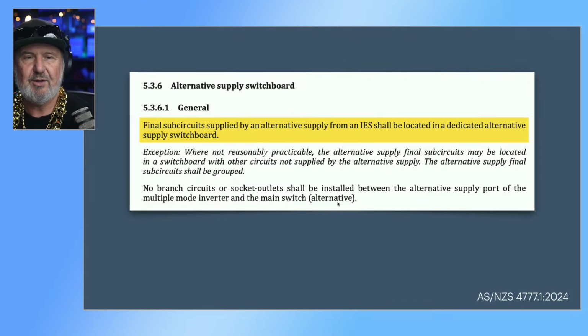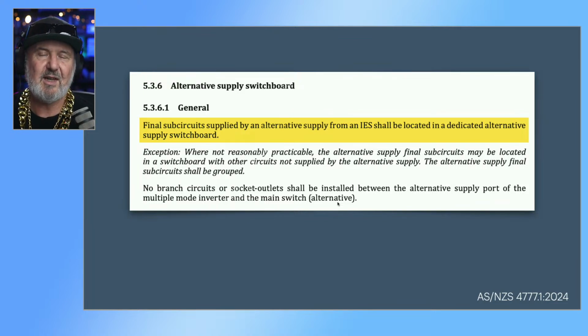So, alternative supply is the new supply naming used. Well, it's not that new to 3000, but it's new to 4777 part 1 for a backup circuit. If you have a hybrid inverter that has a backup, it's now known as an alternative supply. It's an alternative to the normal supply, which is the grid. So it's kind of logical, and we decided that as much as possible, we'll align with 3000 for any of our supply names.